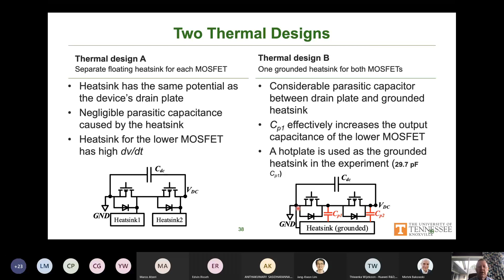However, what we found is that this larger heatsink's effective plane leads to a larger effective capacitance between it and the devices themselves. So let's look at the differences between thermal design A, which is separate heatsinks, and thermal design B, one large heatsink. Also, this large heatsink is grounded, whereas the two separate heat sinks are floating or not grounded.